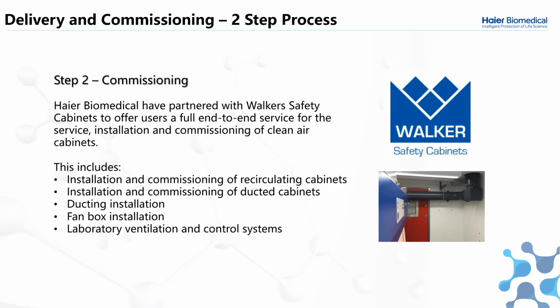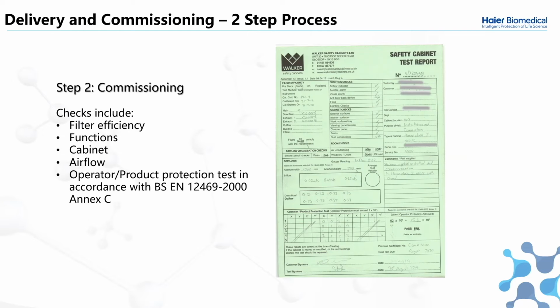By having the Walker name tied to the Haier Biomedical name, it has also given the customer a great deal of confidence in our equipment, as Walker are happy to work with our cabinets and recommend them to their customers. And a great relationship with a local commissioning and installation team can be tremendously helpful when pushing into new markets. Here is an example of one of the Walker test reports, which goes to the standard EN 12469-2000 Annex C in the UK. We test things such as filter efficiency and function, cabinet airflow, operator, and product protection.